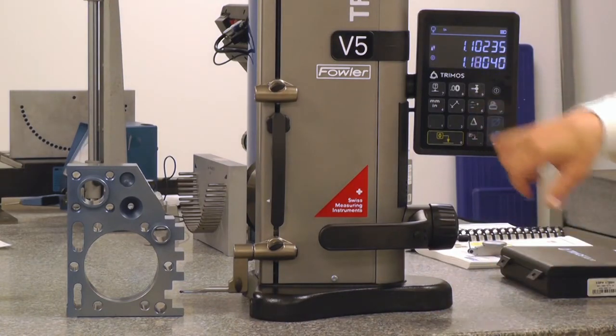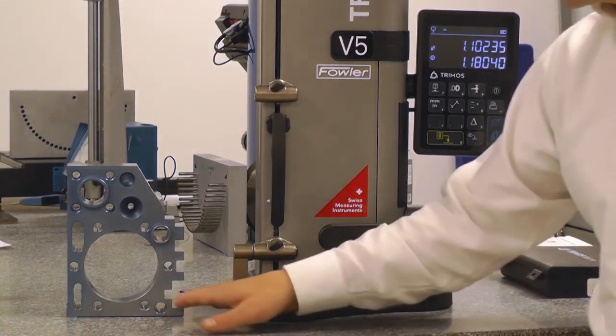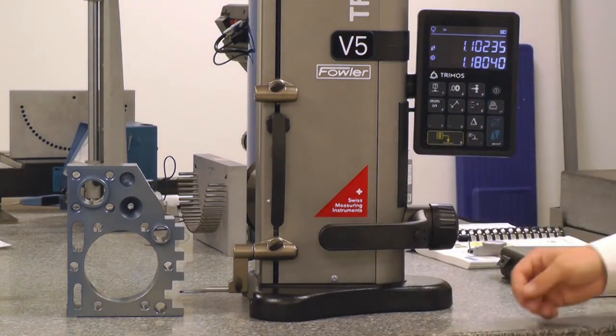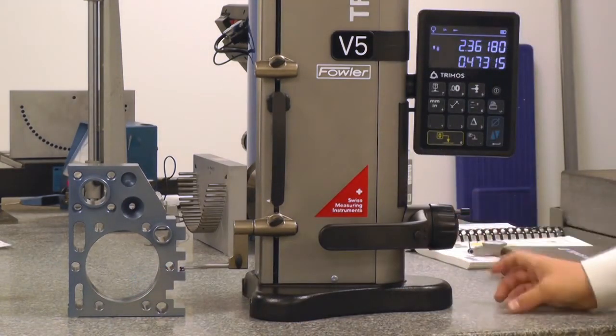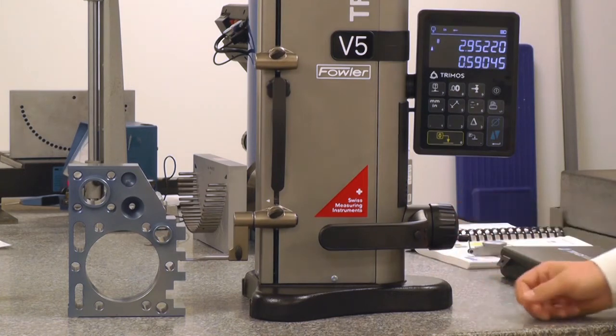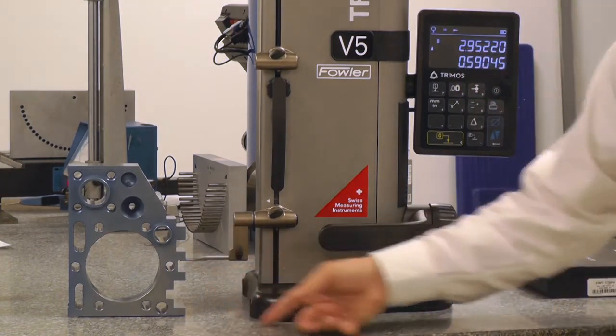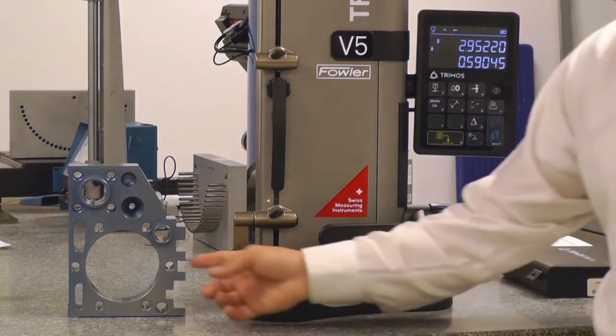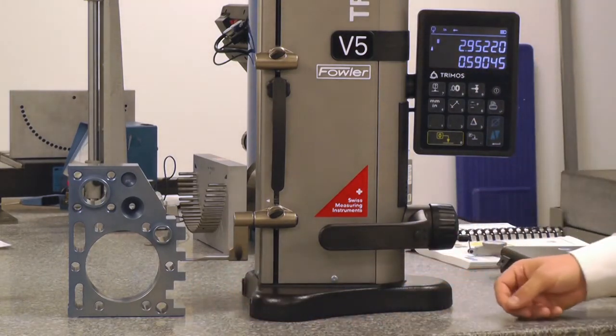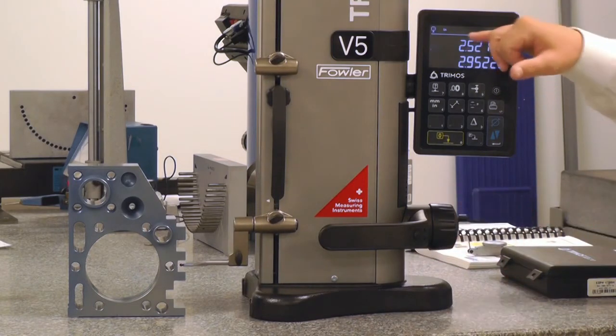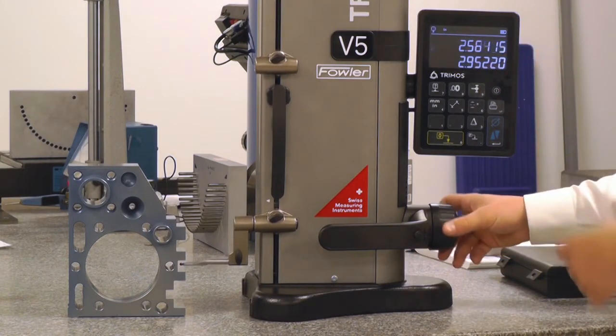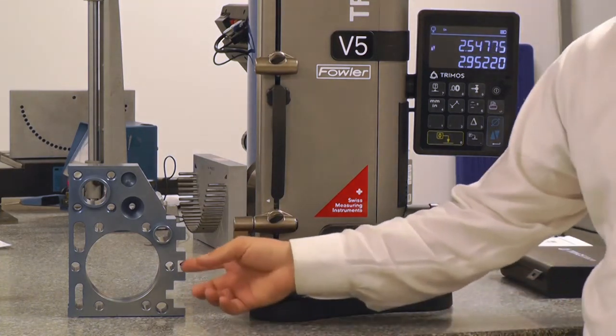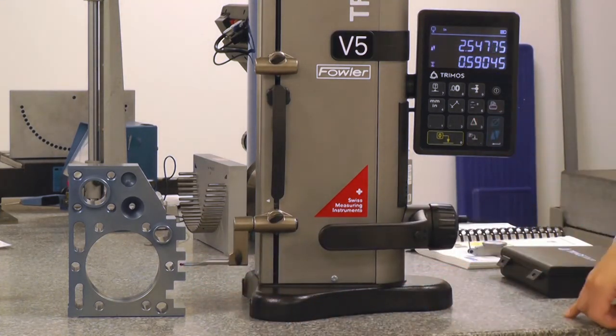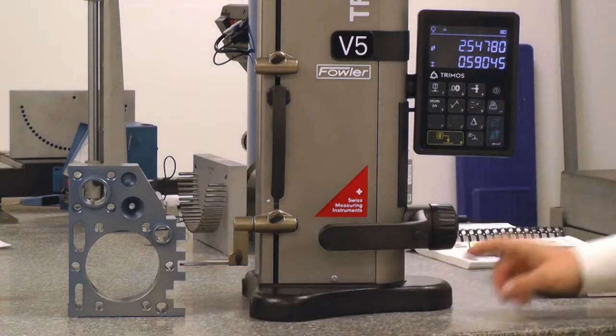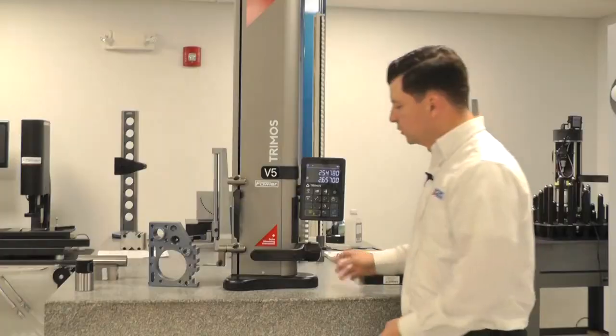If I hit the number 6 key, a center line callout, this is going to establish a center line for those last two features. So again, I could do that on any two features. If I measure the bottom of this land and then the high side, 2.95 from the probe to the plate, 590 thousandths is automatically calculating the difference between the last two. If I release the contact, my last measurement drops down and I have a live indicator on the top. If I want to recall that slot width, I just ask for it by hitting the delta key, and if I want to know the center line of that slot, I hit the center line button. So that's what those buttons will do.